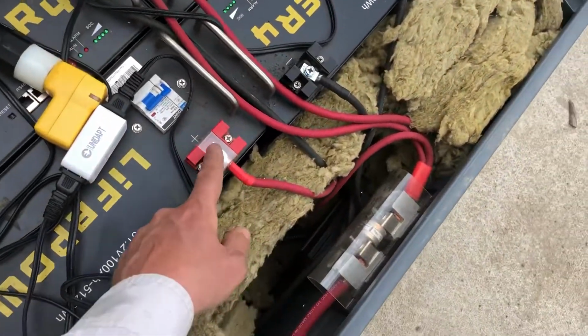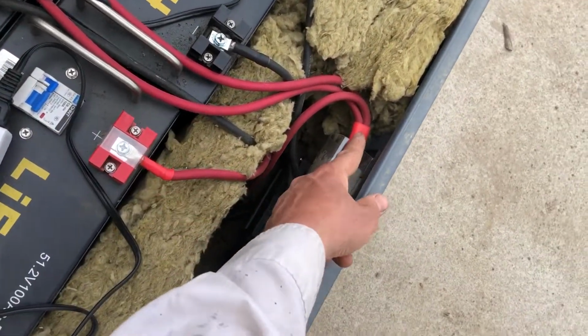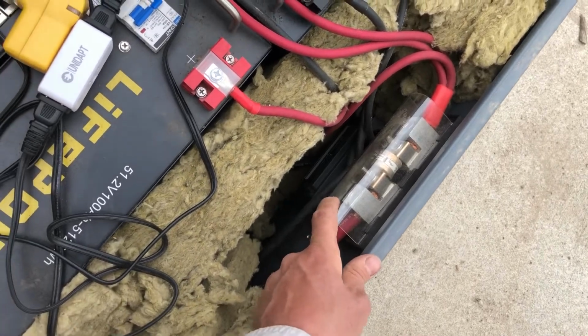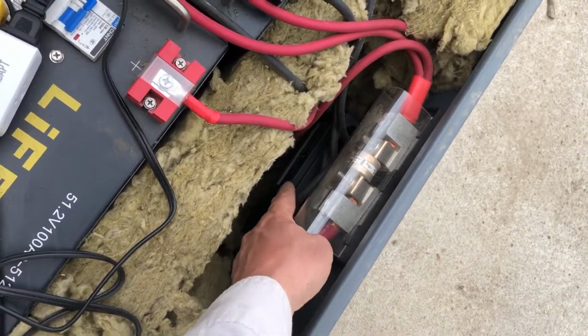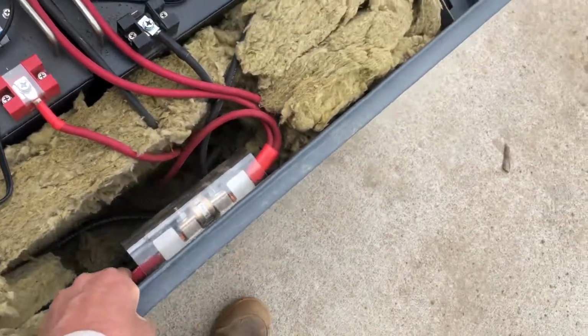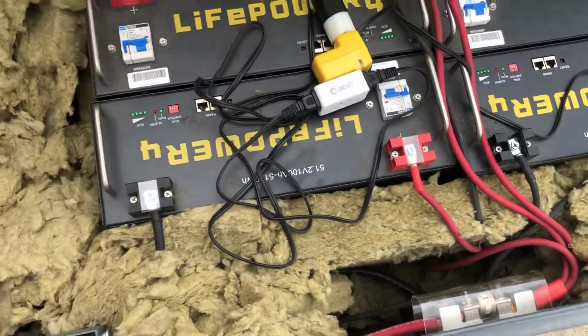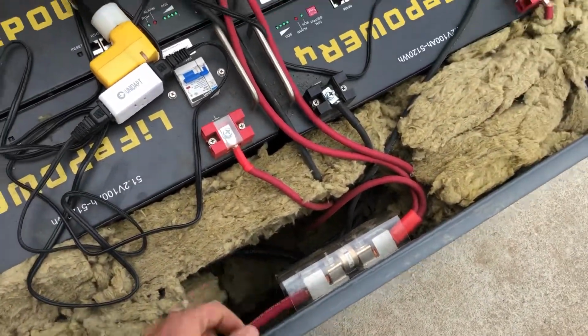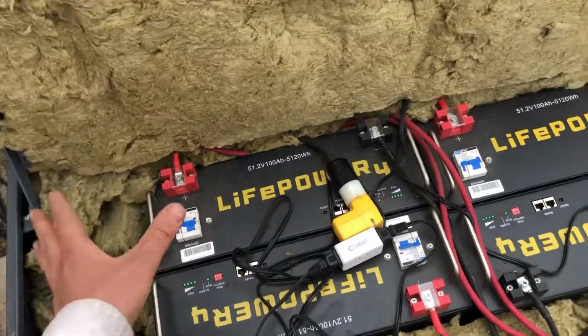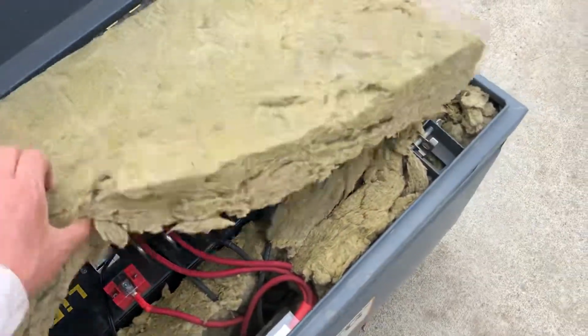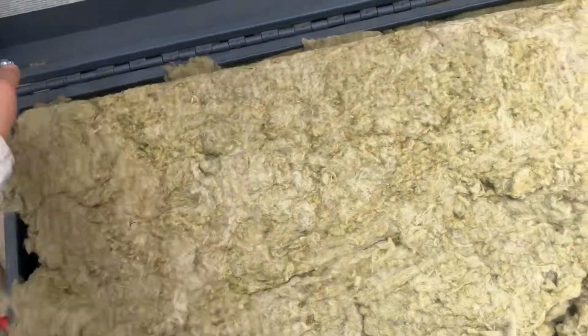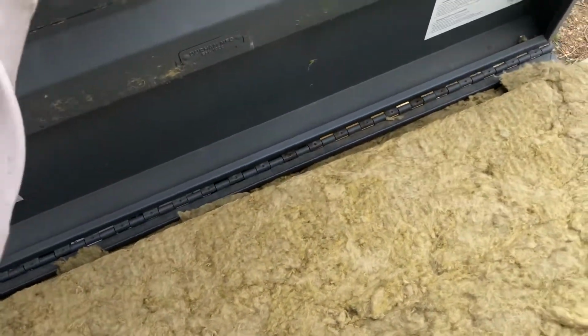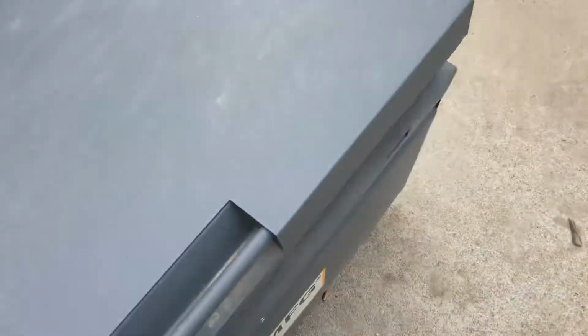And then all of these combine in this fuse here. I think this is a 150 amp fuse, and there's a little bus bar down there for the negatives. And that's the battery system. It's extremely simple. This is mineral wool, completely non-combustible. I would prefer that the fire department show up and look at my steel box with non-combustibles and say, boy, that looks hot.